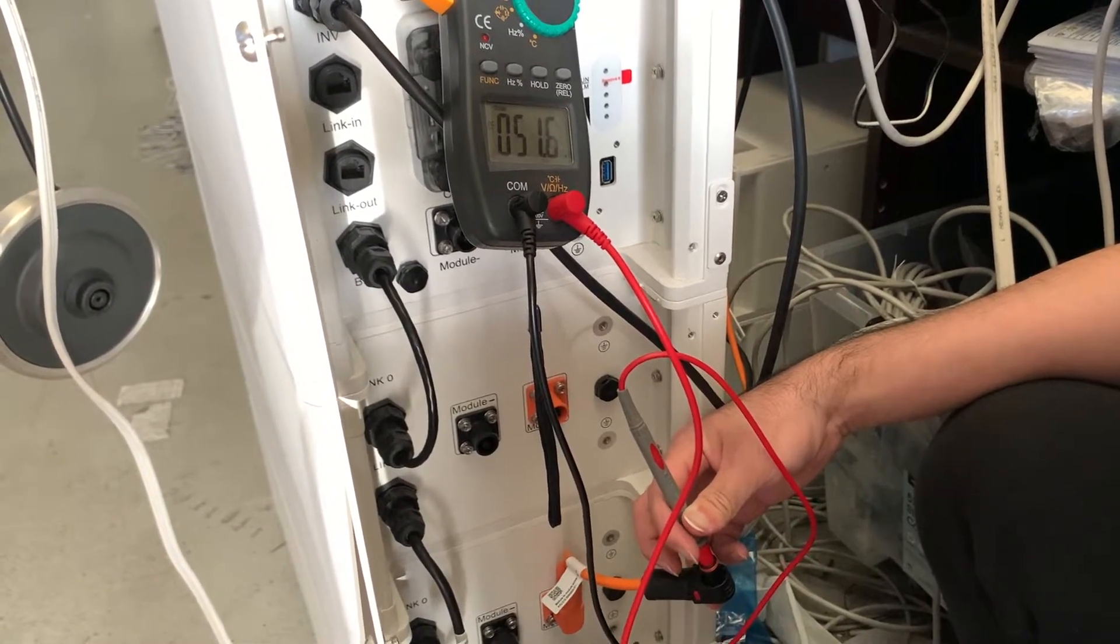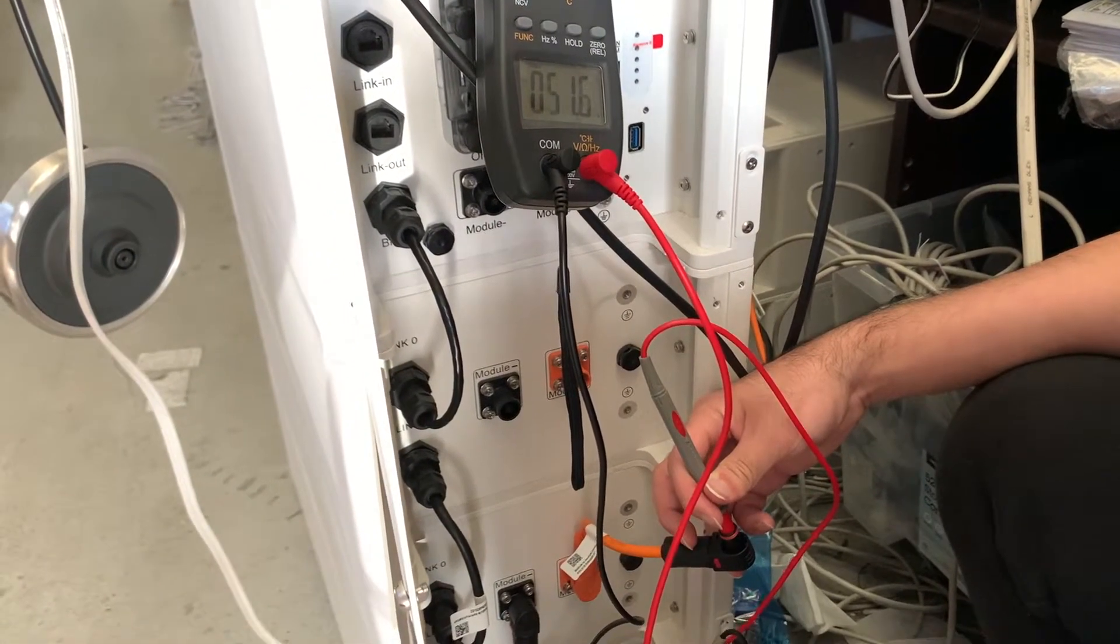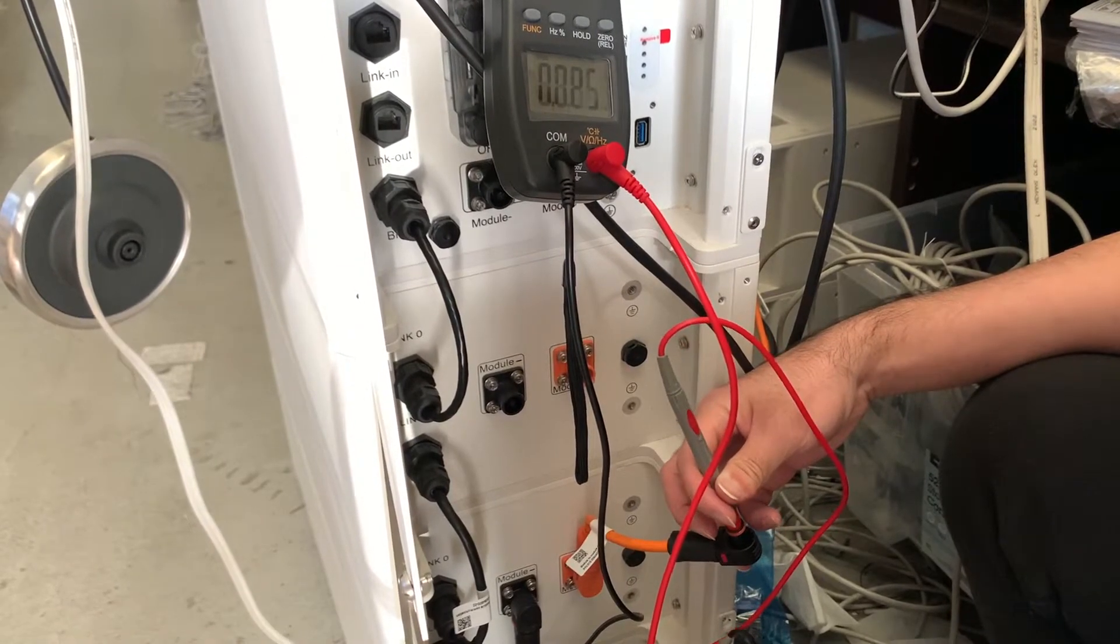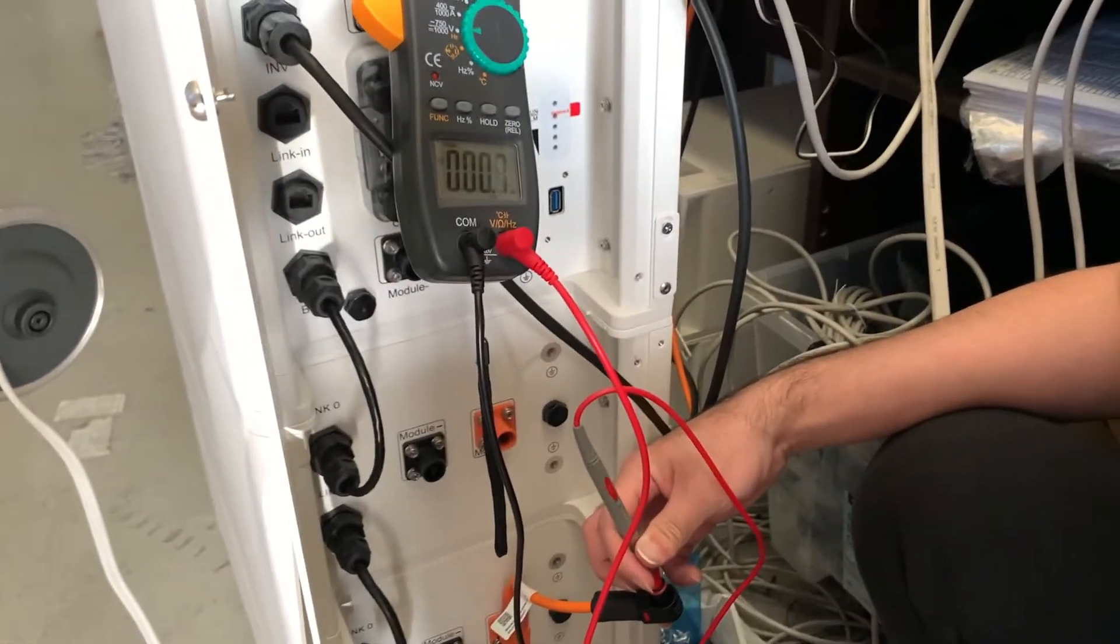Once the voltage drops below 48, there might be something wrong with the battery, and you might need to send back the ARC batteries to us to recharge the battery.